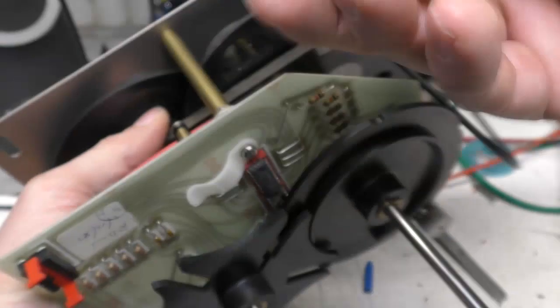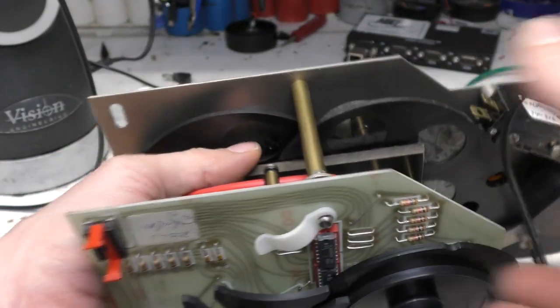Considering the actual trigger transformer, which we'll see on the main board, is quite small, it's just really poor design to not mount that either on this part here or perhaps this base here. Maybe if this is a replaceable part, you wouldn't mount it on there, but they could certainly have mounted it on this socket and then had a relatively low voltage signal up to trigger it. So that's not too impressive.